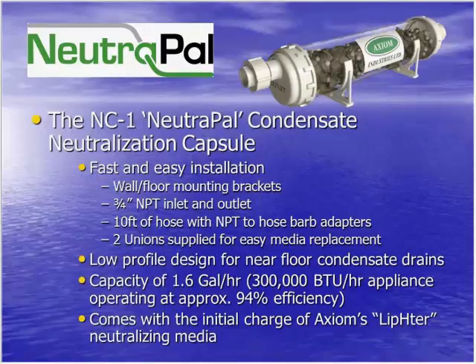And we offer sizing calculators on our website that you can simply input the BTU input and the AFUE efficiency of the appliance, and it will select an appropriate neutralizer for your application. I think that 1 gallon per hour per 100,000 BTU capacity is probably a snowmelt system in the Arctic. Yeah. Cold startup, acceleration conditions with a 99% thermal efficiency factor. Rare.